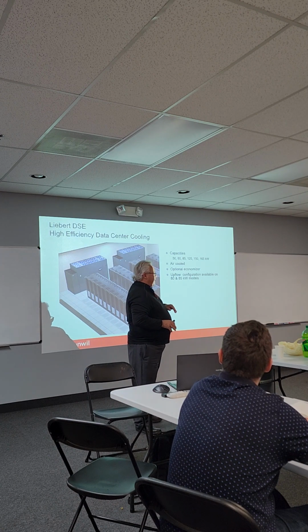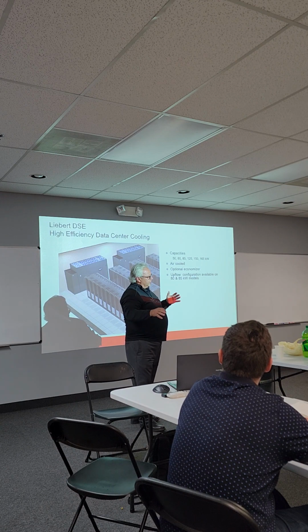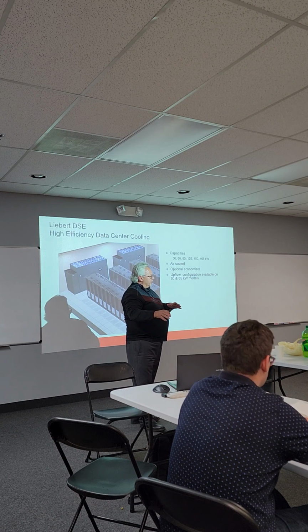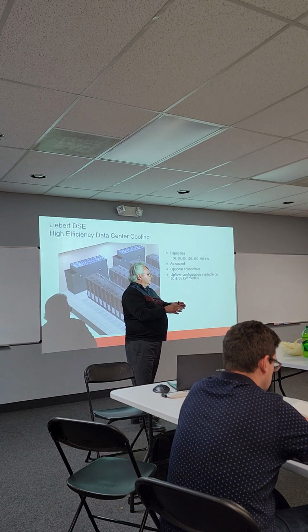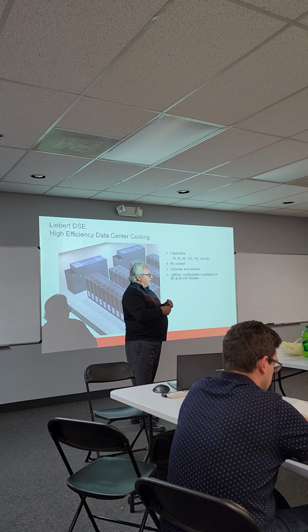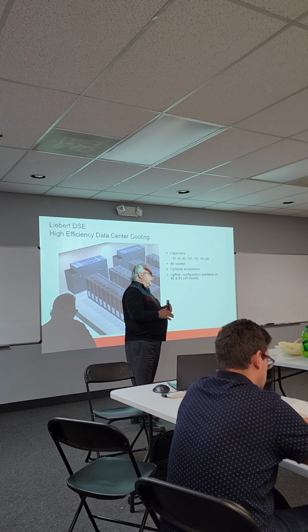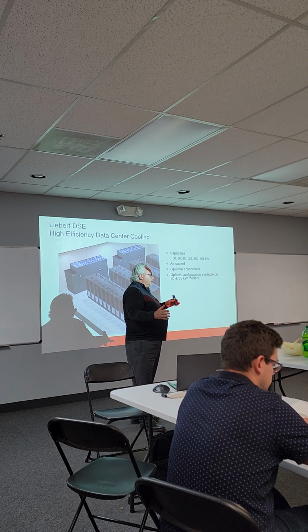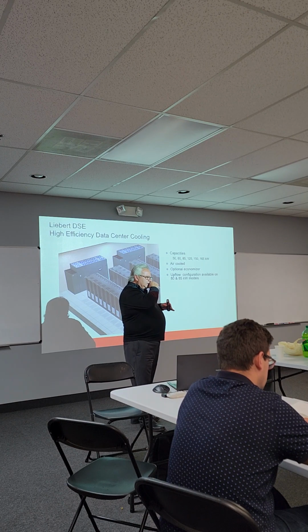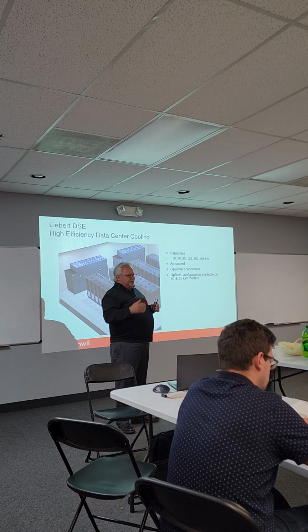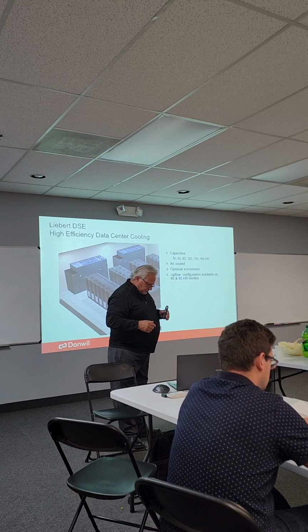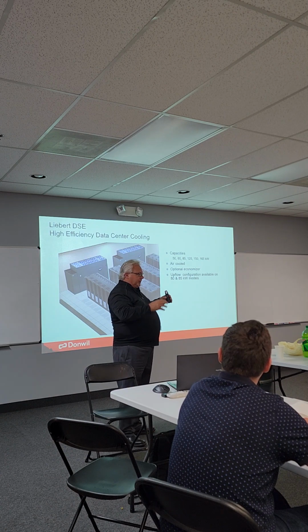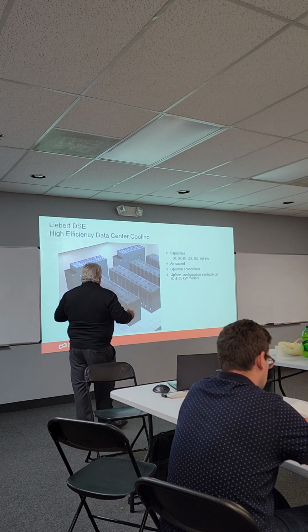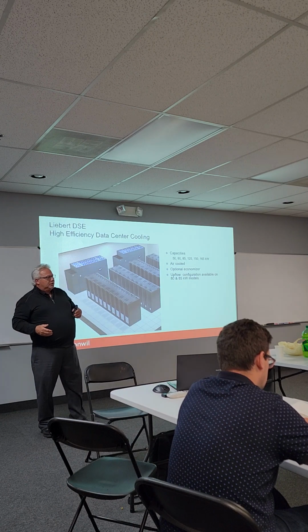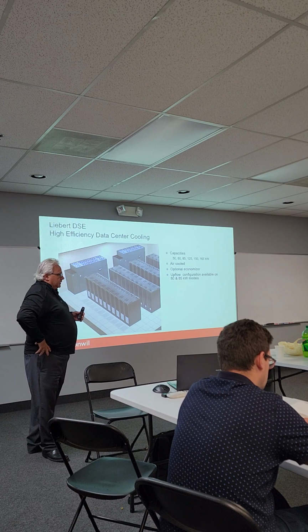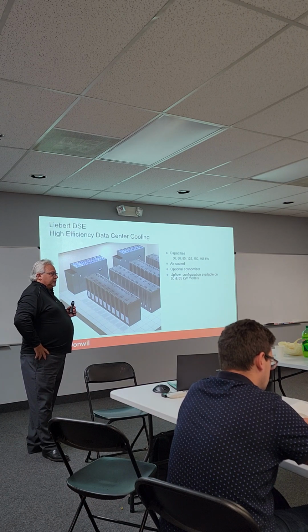All right, so the best thing to do, since anything that's in the computer room is drawn off of the UPS power, like their servers and whatnot, if you go to their UPS and you see what the kW draw is, you can pretty much figure out what the load in the room is. It's not going to be exact, but let's say you've got a 100 kVA UPS. You go to that UPS, you say to the IT guy, hey, can you tell me what the kW draw is on the unit? He tells you, yeah, I'm drawing 45 kW right now. You take that times 3.413 and that's going to give you your load basically, so that you can tell in BTUs what you actually have.